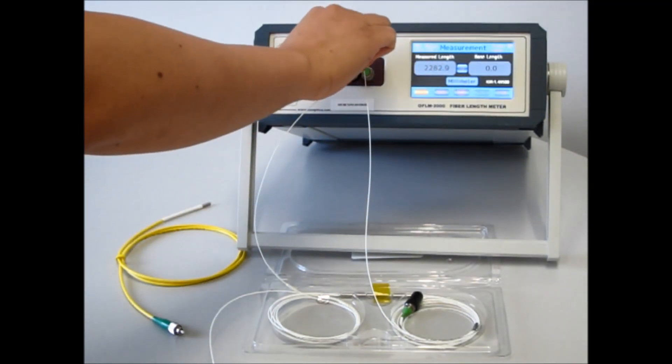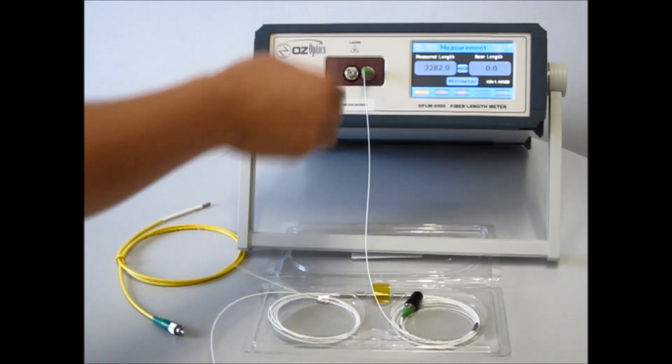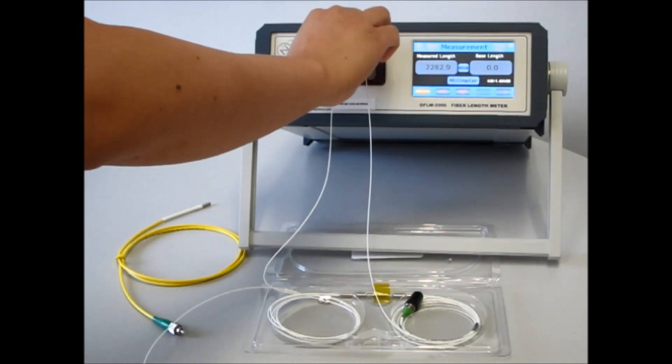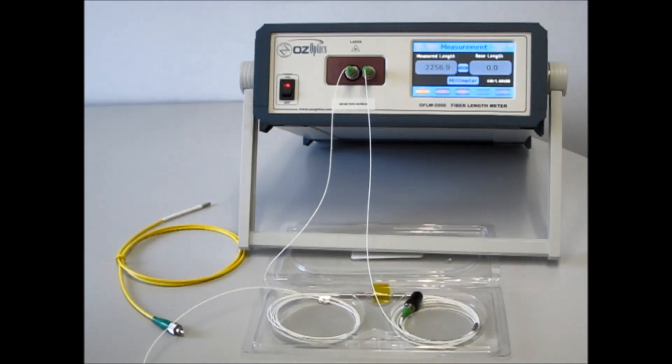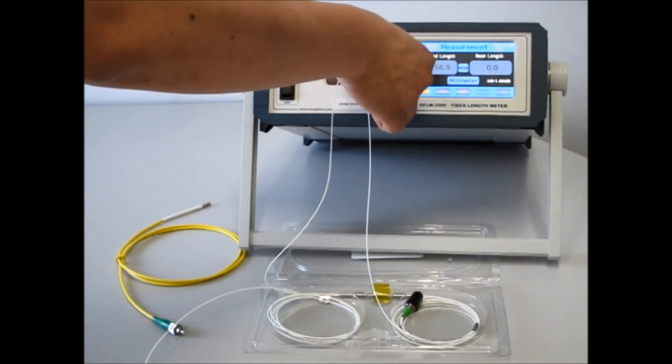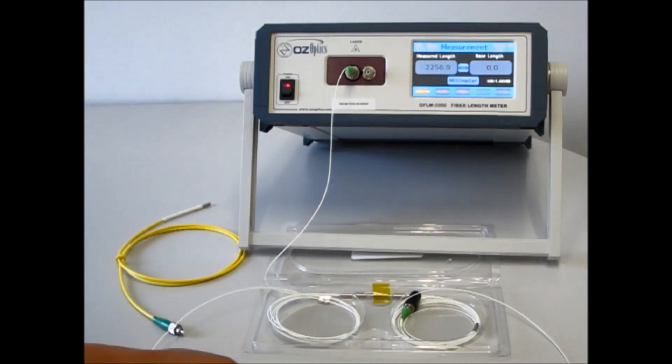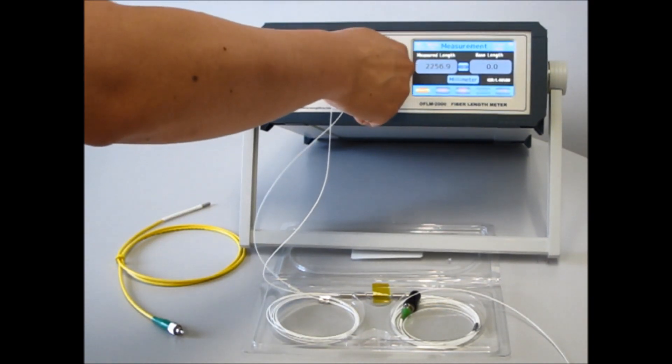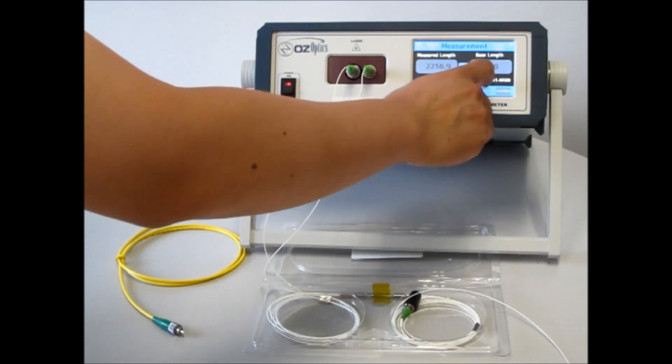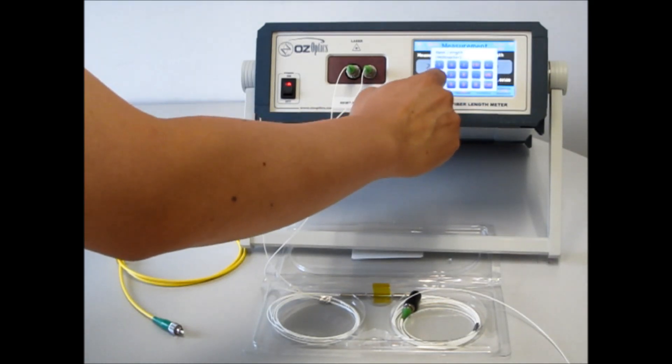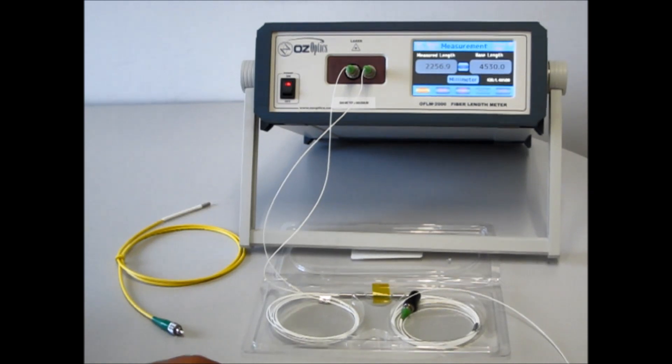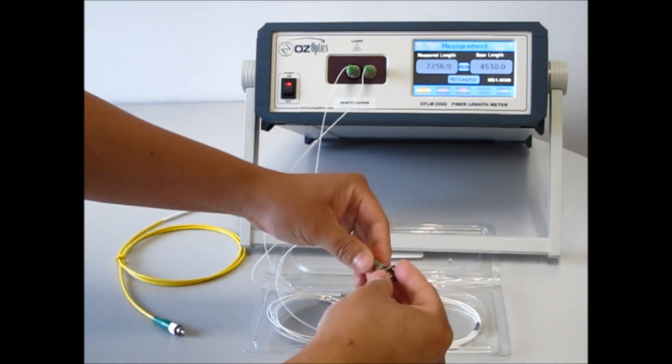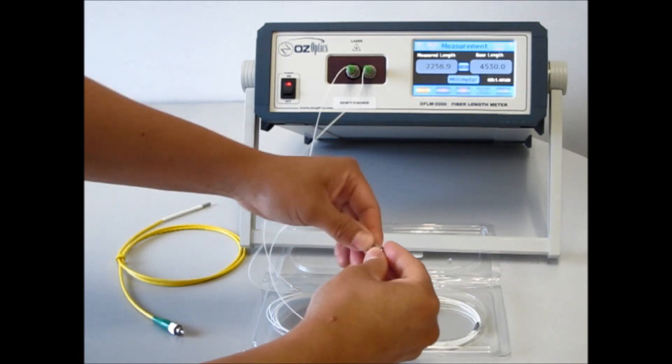And now we're going to measure the length of the return path. Add these two lengths together to get the total length of the fiber added due to the splitter. Now return both ports back into the fiber length meter. Now we can manually type in the base length of about 4.5 meters. Okay. And add a mating sleeve to the end. And now you have a calibrated one-port fiber length meter.